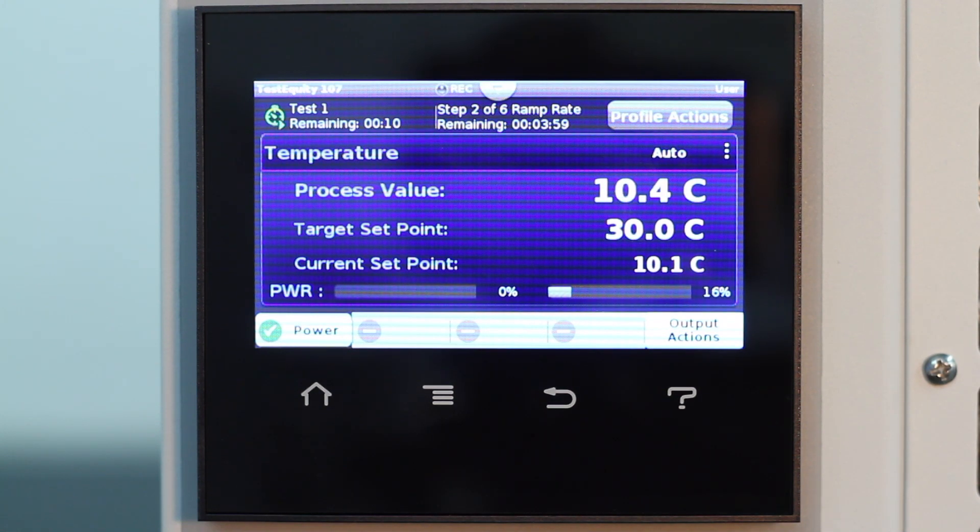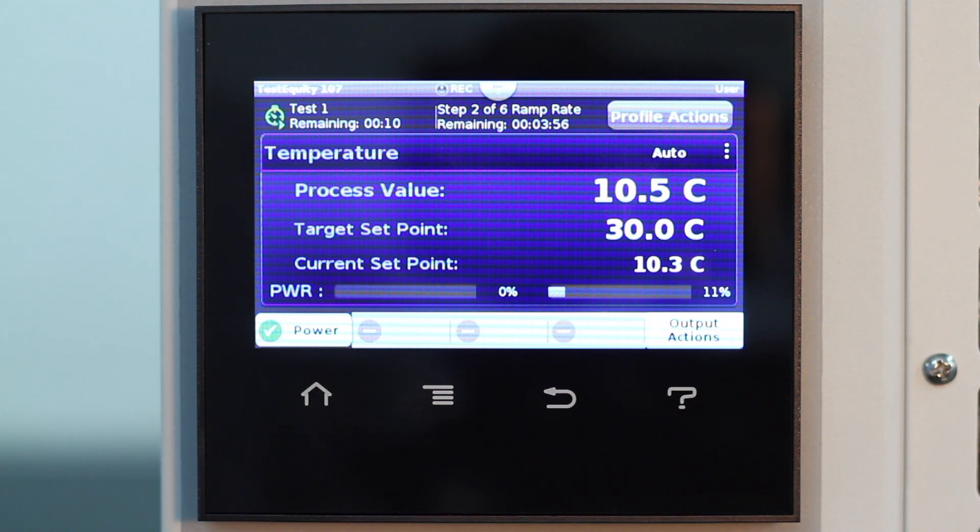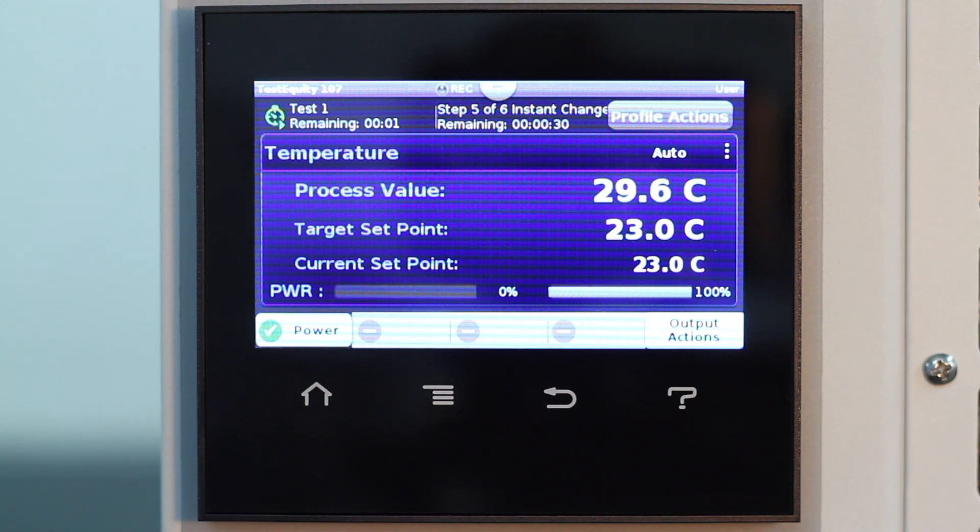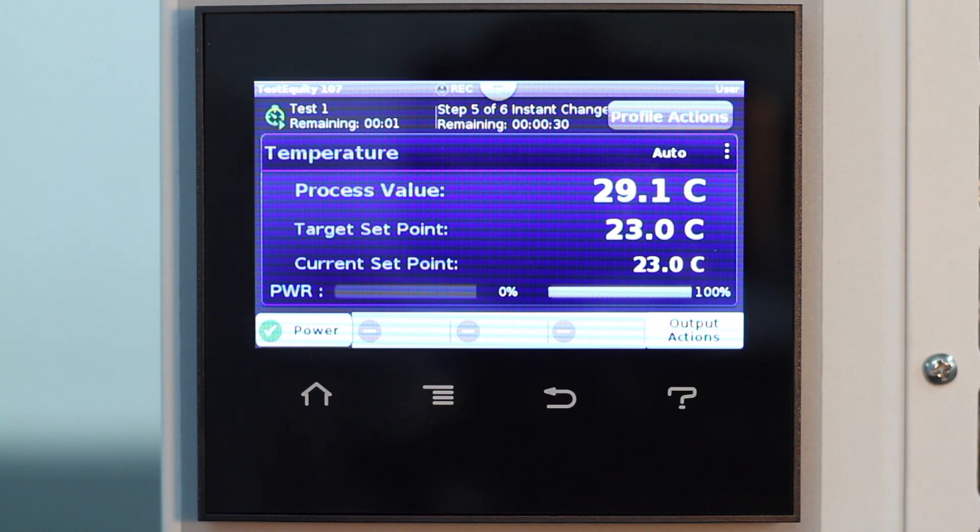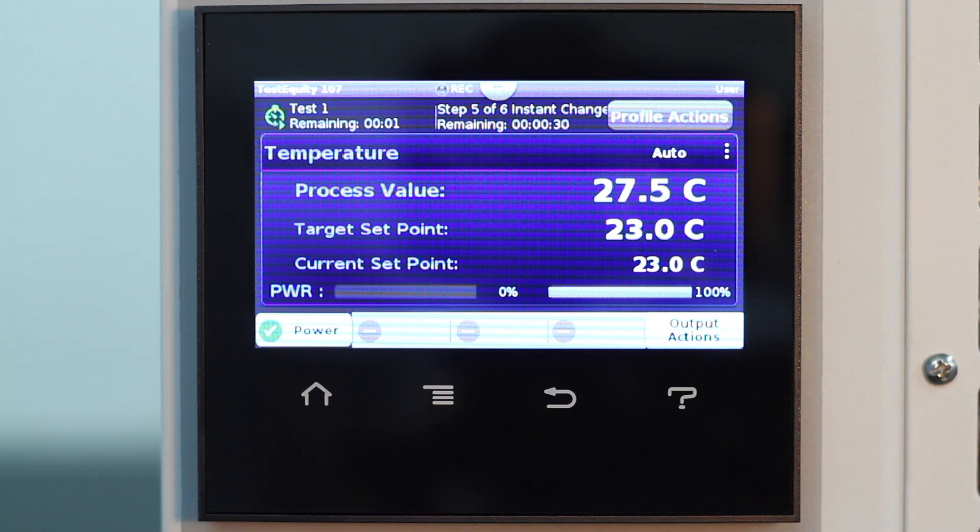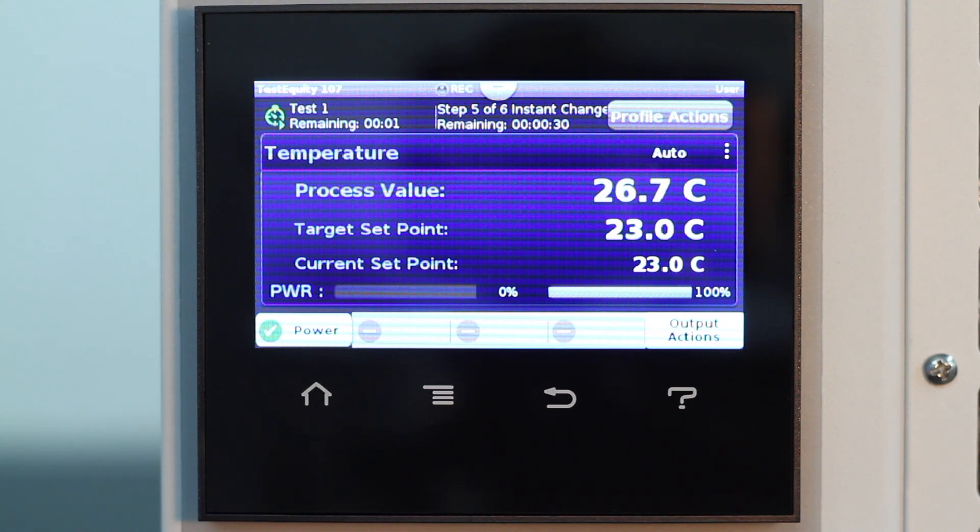Now you can see the next step ramping up to 30 degrees C at a rate of 5 degrees C per minute. Here is the next to last step, returning to 23 degrees C, beginning the 30 second soak time when the chamber is within the 1 degree soak deviation value, which for this step translates to 24 degrees C.